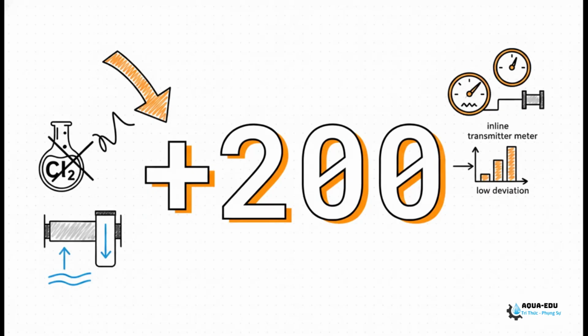So here is the absolute crucial point, guys. Your normal operating ORP must stay below positive 200 millivolts, or whatever your specific plant design set point happens to be. Seeing this consistently low reading confirms complete chlorine removal right at the RO inlet. Also, keep an eye on the deviation between your inline transmitter and your handheld meter. That difference must be less than 15 millivolts.